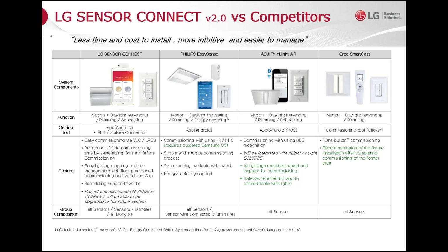One of the limitations, though, in commissioning Acuity Nlight Air is that everything must be mapped before commissioning, and you need a gateway to talk to the lights. You can't talk to the lights directly. So although they support Android and iOS, they're supporting it using Bluetooth, but that Bluetooth connects to the gateway through the phone's Wi-Fi connection. That means if you're too far away from a gateway or the gateway loses power, you lose communication with the light.